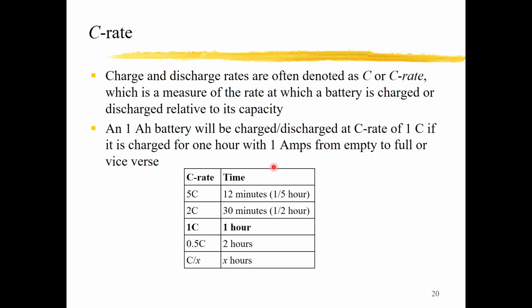And with the C rate, we can also quickly understand how much time is required to charge the battery to the full state. For example, if I use a 1C current to charge the battery, then we expect the battery will be fully charged after 1 hour. And if I use only 0.5C rate, then it takes 2 hours. And if I use 5C rate, then it takes only 1/5 hour, or 12 minutes. Maybe you have heard that some EV charging stations say they can charge your battery within 20 minutes. Then you can quickly understand how much C rate it is talking about.